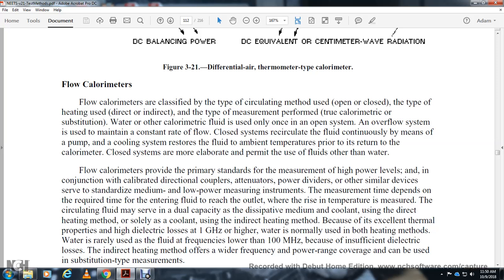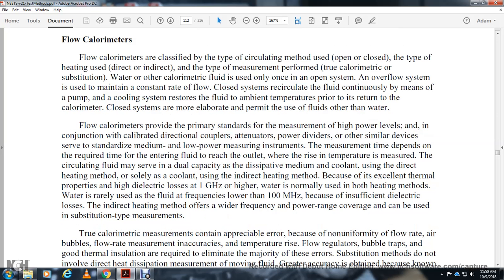The overflow of the system maintains the constant rate of flow. The closed system recirculates the fluid continuously by means of the pump of the cooling system, or cools the fluid to the ambient temperature prior to the return to the calorimeter. Closed systems are more elaborate and permit the use of fluids other than water. Flow calorimeters provide the primary standard for the measurement of high power levels in conjunction with the calibrated directional couplers, attenuators, power dividers, and any similar device that serves as a standard for medium and low power measuring instruments.